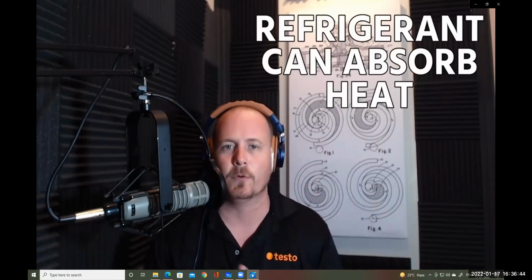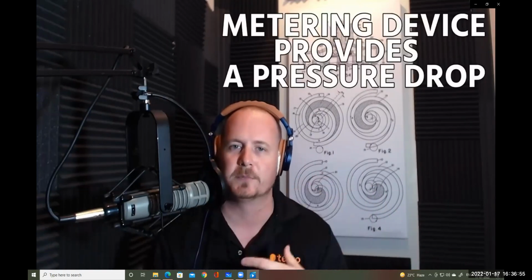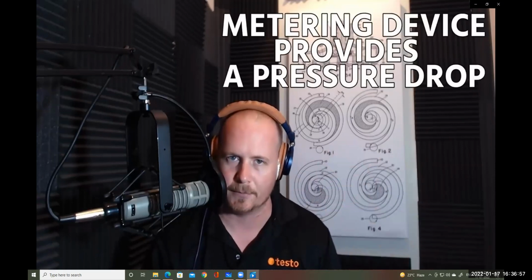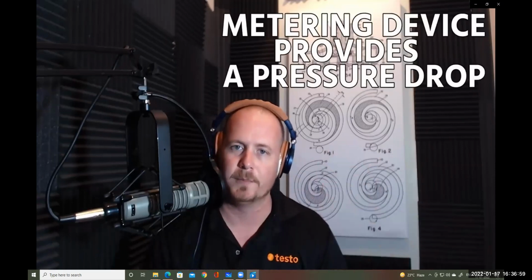And like we talked about before, the reason why the evaporator coil is cooler, a lower temperature than the other components, is because there's a pressure drop right before it. We're going to talk about the metering device separately, but the metering device provides a pressure drop going into the evaporator coil, and so that evaporator coil can be a lower temperature.